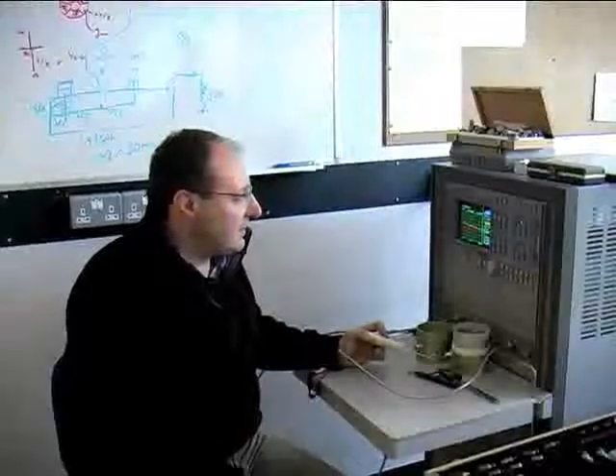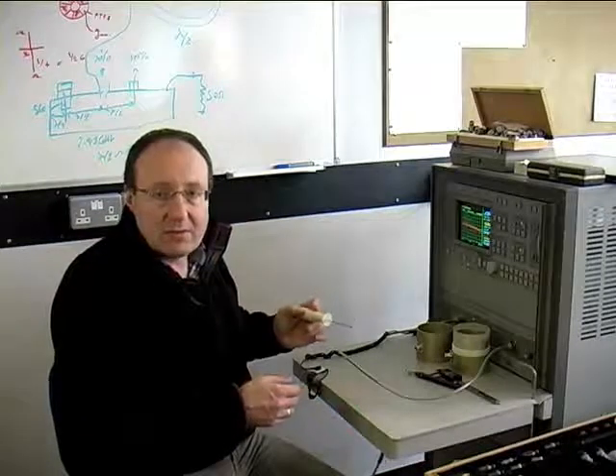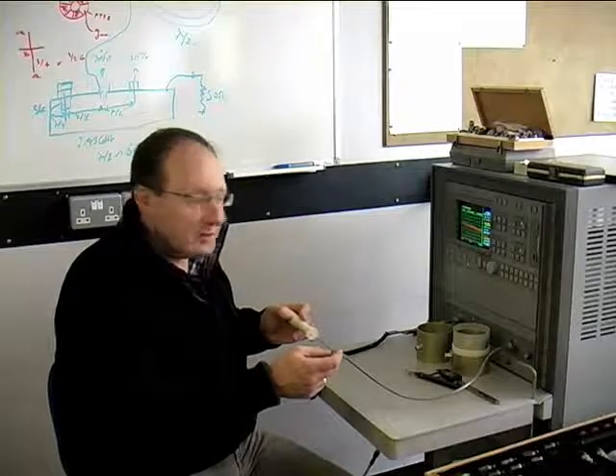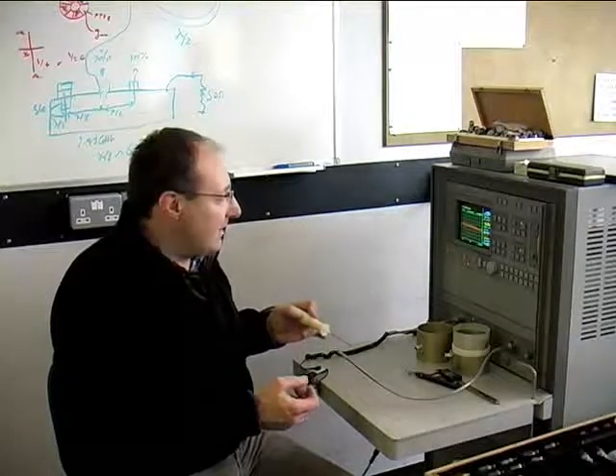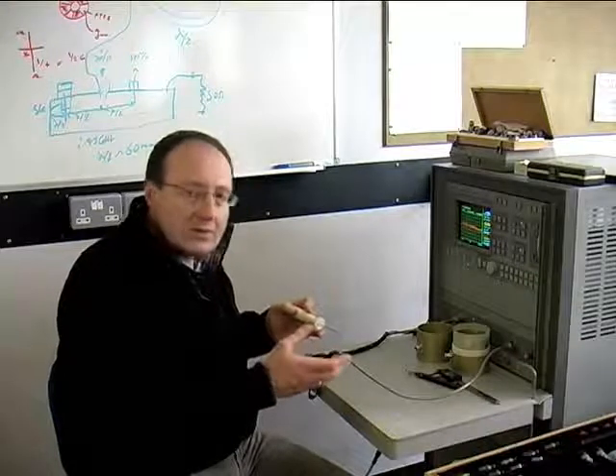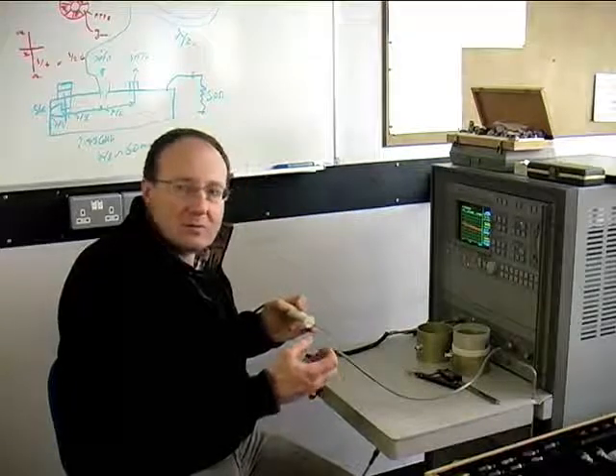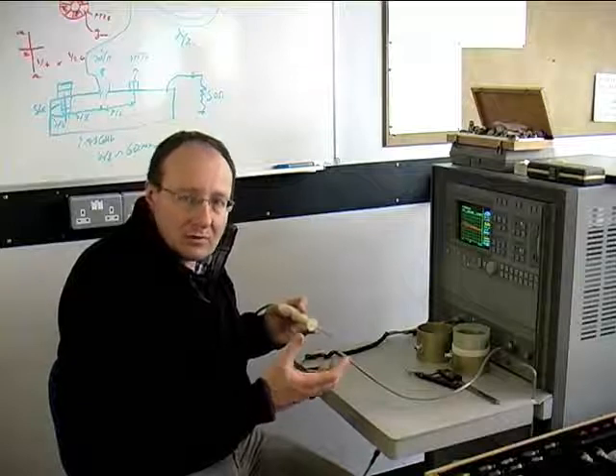This is one of the main pieces of test and measurement equipment used for setting up the actual antennas used to treat various types of tumors within the human body. This structure was developed for treating breast cancer. The tip of the antenna measures the properties of the tissue — its dielectric properties — which are displayed on this network analyzer. Once we identify the tumor's characteristics, it can then be used to deliver focused, controlled microwave energy into the tumor to ablate it: heating the tissue to cause proteins to denature and destroy the cancerous cells.